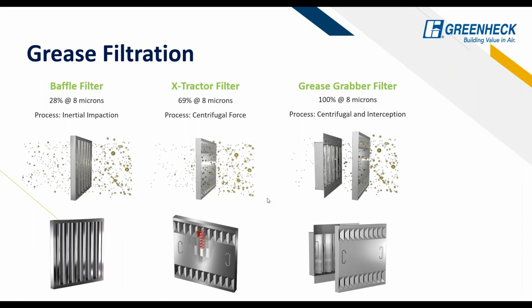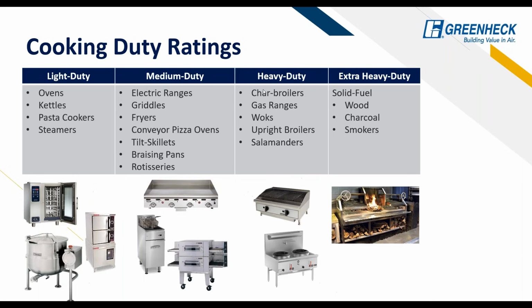So baffle filters are just the inertial impaction there, just like a typical filter. And then the X-Tractor filter uses centrifugal force. You can actually see it down here. So air passes through this, and it actually creates this corkscrew style airflow pattern, which is also pushing grease particles to the filter in addition to the inertial impact. And then the grease grabber will do both of that and get about 100% there. So different options. Most of the time, you're probably going to be in this middle range. That is the most commonly used.